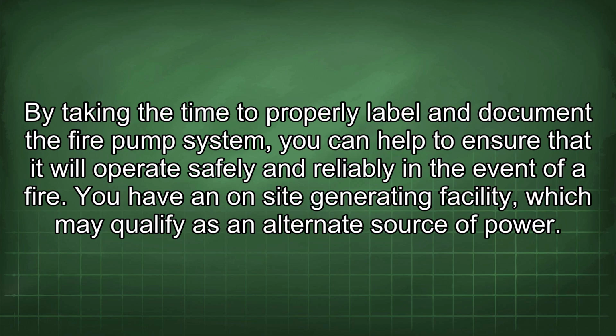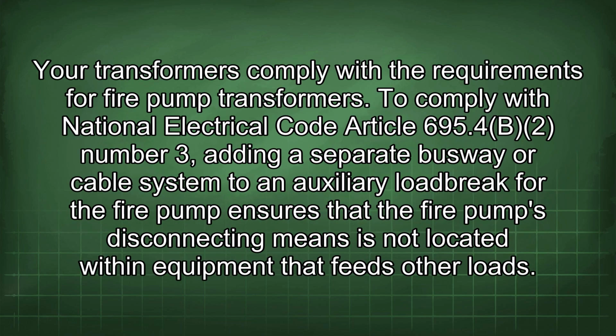You have an on-site generating facility, which may qualify as an alternate source of power. Your transformers comply with the requirements for fire pump transformers. To comply with National Electrical Code Article 695.4 B2 number 3, adding a separate busway or cable system to an auxiliary load break for the fire pump ensures that the fire pump's disconnecting means is not located within equipment that feeds other loads.